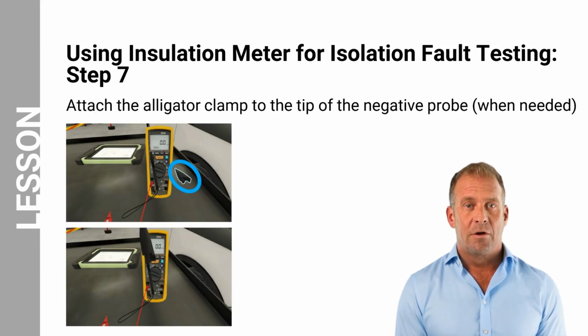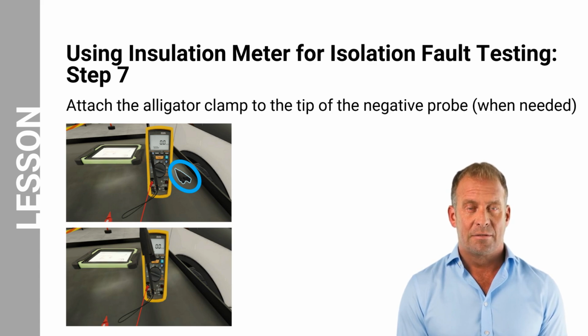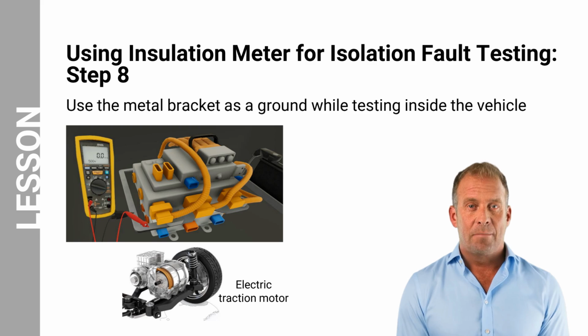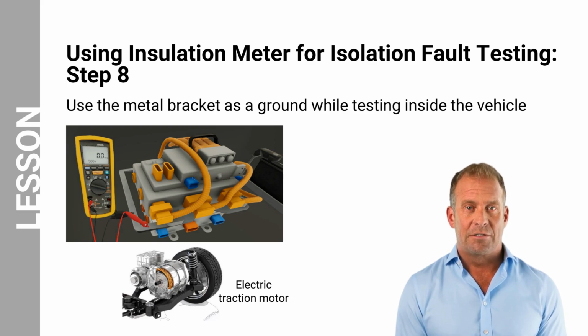Step 7. You need a good ground reference to perform the isolation fault test. Use an alligator clamp when needed to attach the ground test lead. Typically, the reference point will be the vehicle chassis. Step 8. Ensure you verify the ground connection before every test measurement at a suitable ground location near your test point. As an example, we will use a metal bracket as a ground while testing inside the vehicle.